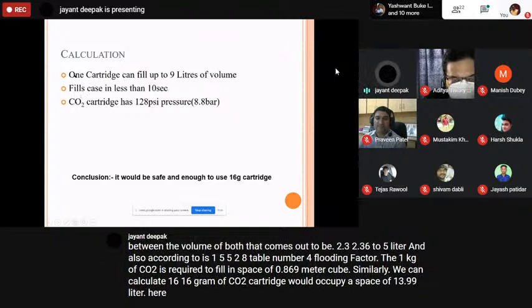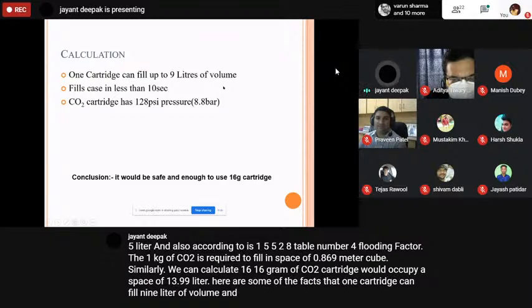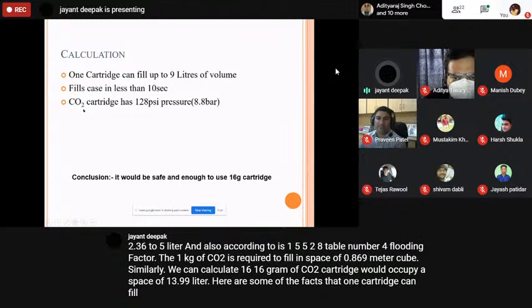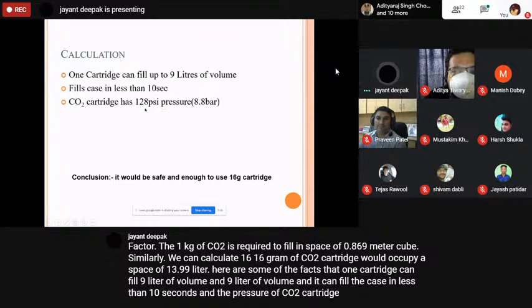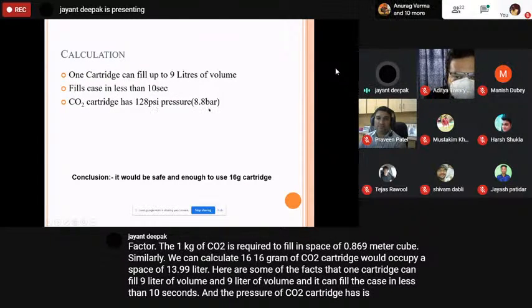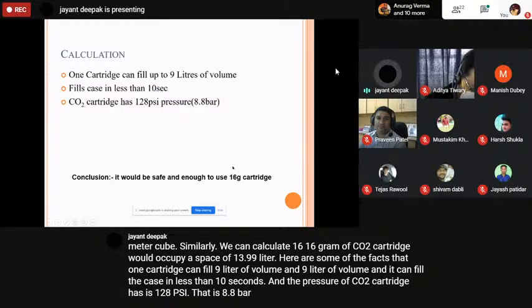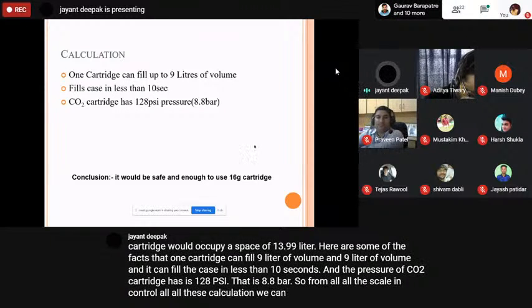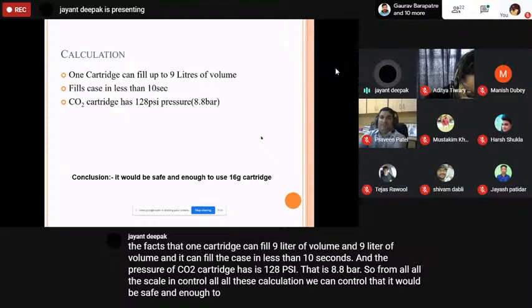Here are some of the facts: one cartridge can fill 9 liter of volume, and it can fill the case in less than 10 seconds, and the pressure the CO2 cartridge has is 128 psi, that is 8.8 bar. So from all this calculation, we can conclude that it would be safe and enough to use a 16 gram CO2 cartridge for our system.